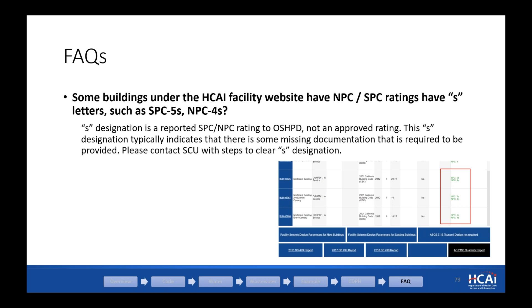Do hospital facilities need to meet the requirements of NPC 5 now? I believe Ali talked about this, and I did too. For existing buildings, the milestone date for NPC 5 is January 1, 2030. Again, there are additional milestones to make sure that we meet that date, but the compliance deadline is January 1, 2030. New seismically separate general acute care hospitals that are greater than 4,000 square feet are required to be NPC 5 compliant at the time of construction. And that's listed in CBC Chapter 16A, as shown here.